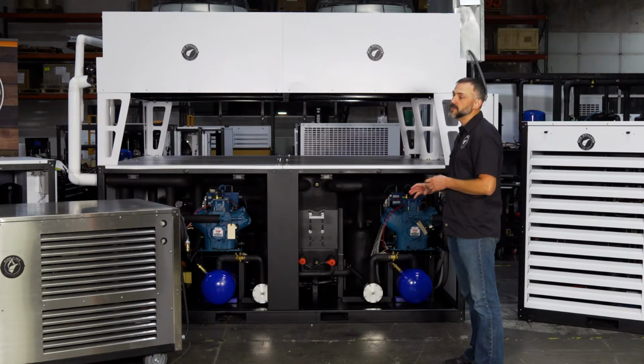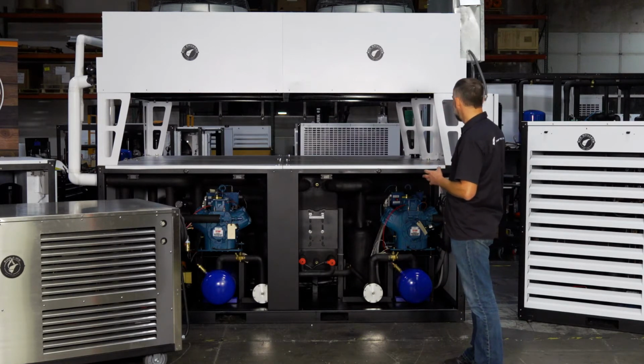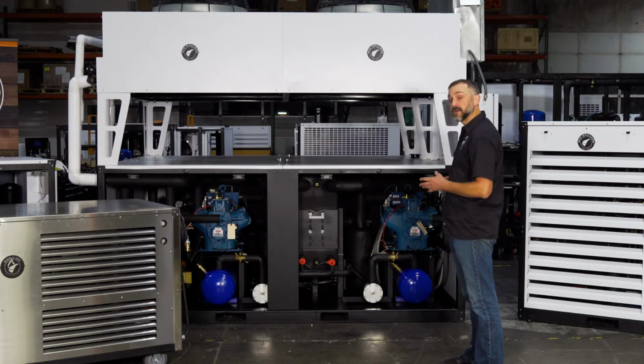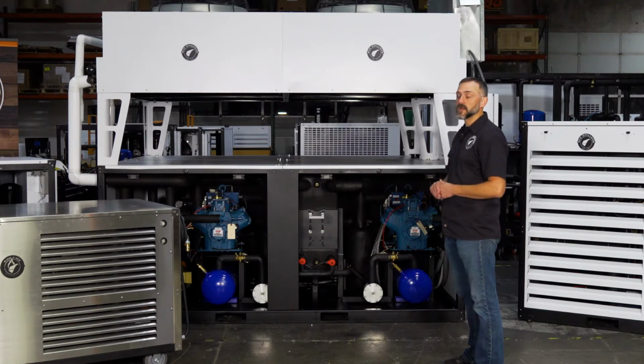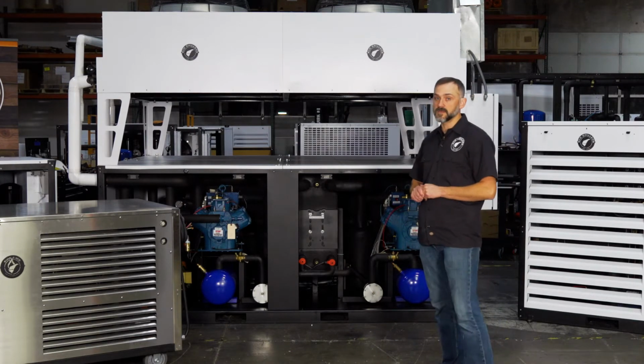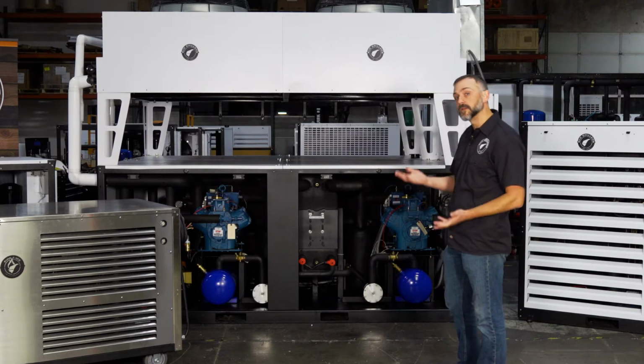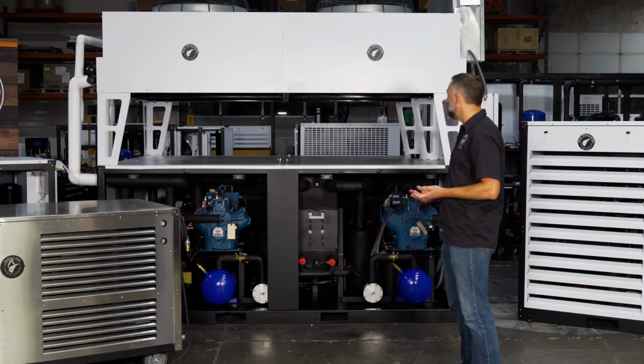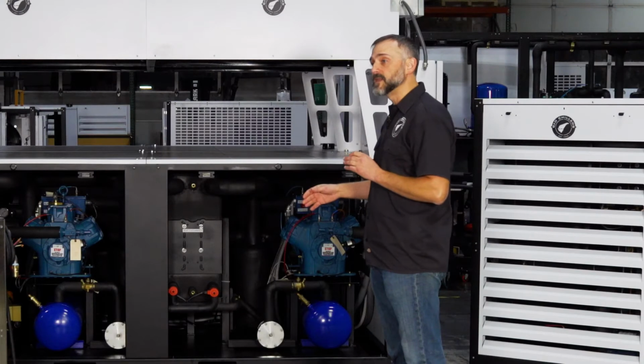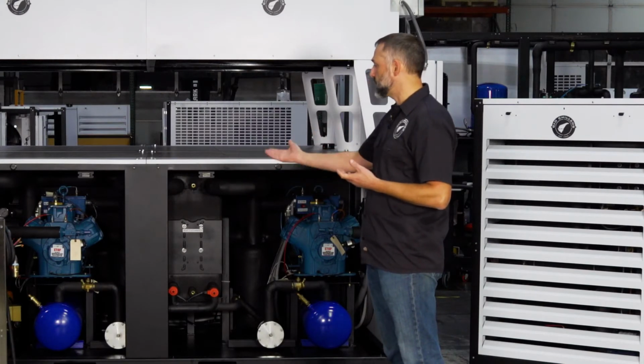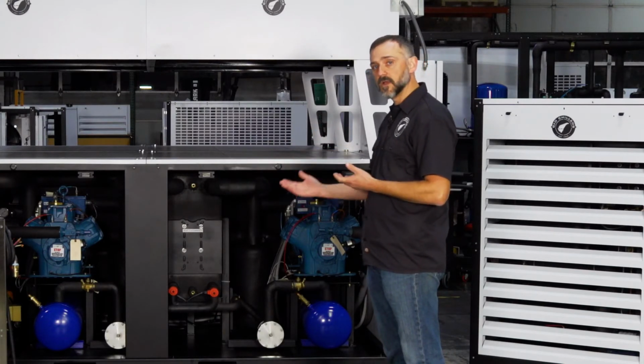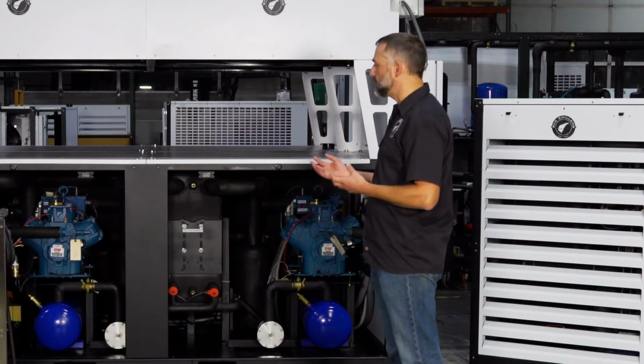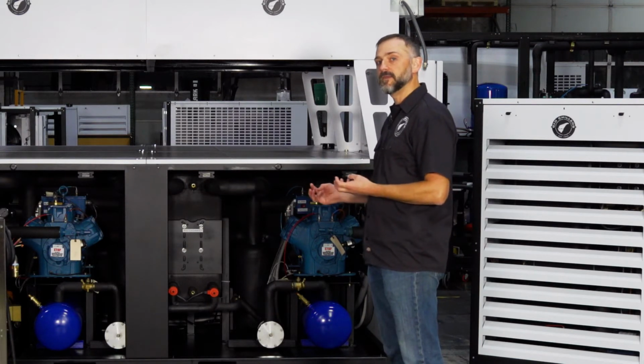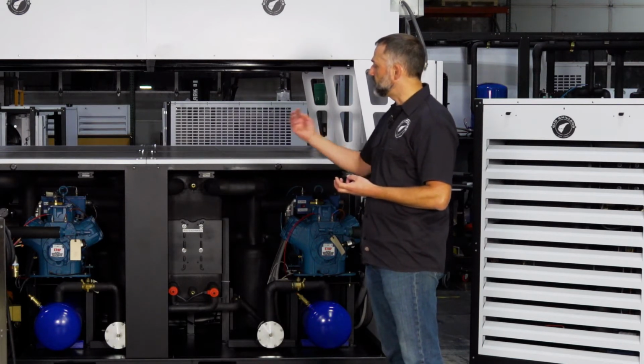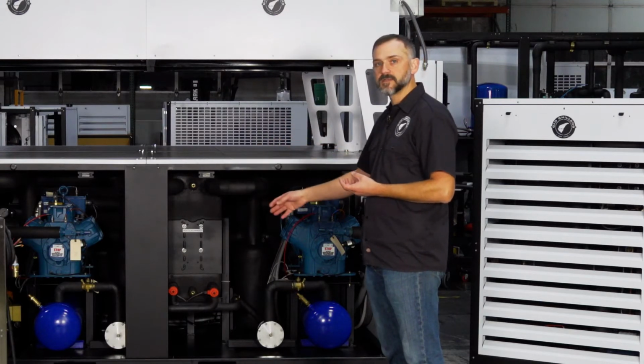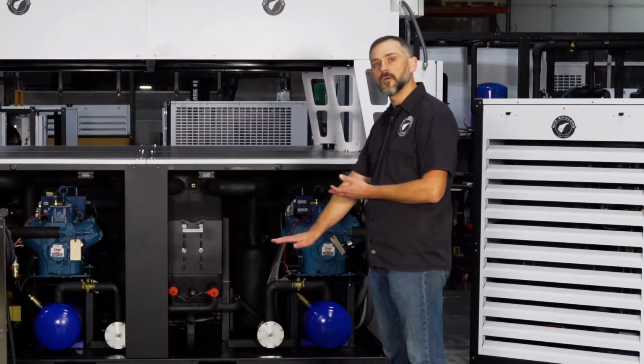The great thing about this unit is that it has 2 stages of chilling. It will run on an as-needed basis, so we're drawing a lesser amount of electricity if it's not needed. There's a lot of fluctuation in load in a winery, so we want to account for that. In addition, these compressors are reciprocating compressors that actually unload as well. So if your demand at any given time doesn't need even the full capacity of one compressor, it's going to kick out some cylinders and operate at even lower capacity.